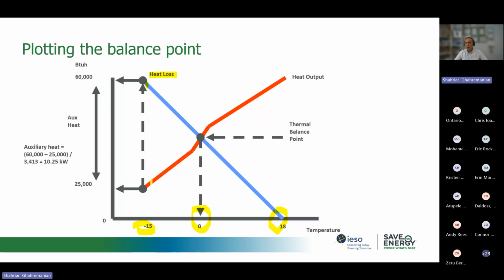And when it's minus 15 degrees Celsius, the building, for example, loses this much: 60,000 BTU per hour, which is almost equal to 17 or 18 kilowatts. This is the amount of heat loss for our building when the outdoor temperature is minus 15 degrees Celsius. Now, the red line represents the heat pump operation. It shows that when it's minus 15 outside, the heat pump can provide this much heat, let's say 25,000 BTU per hour, or almost 7 to 8 kilowatts.